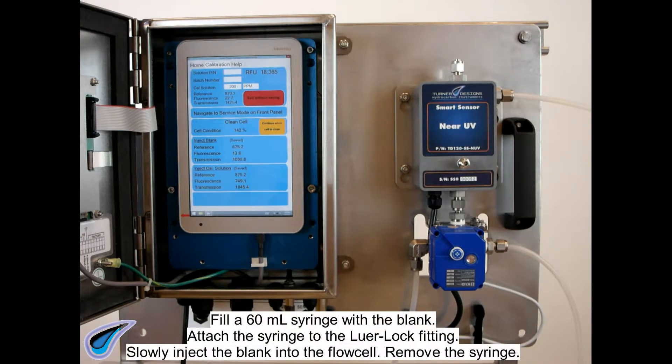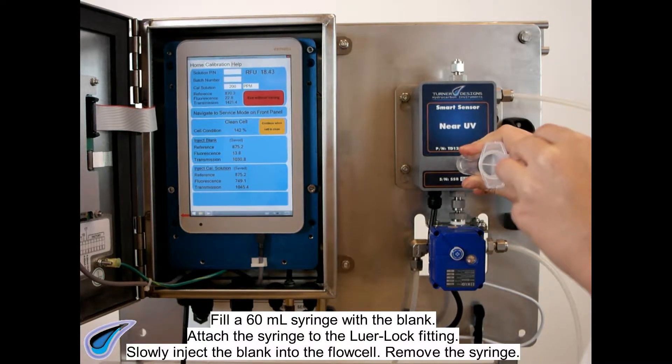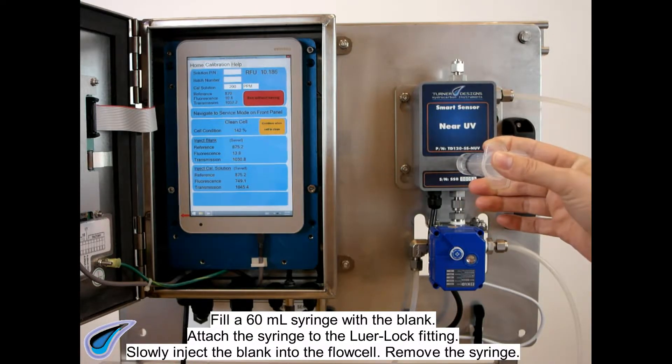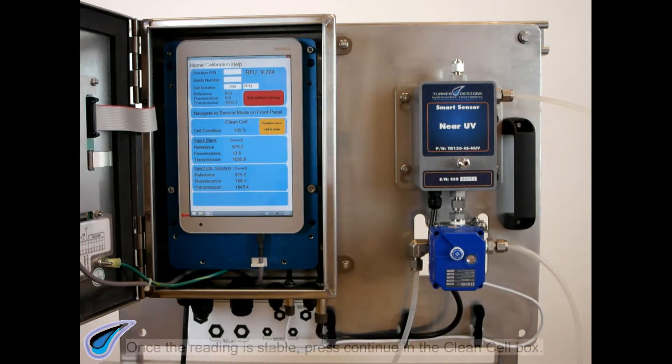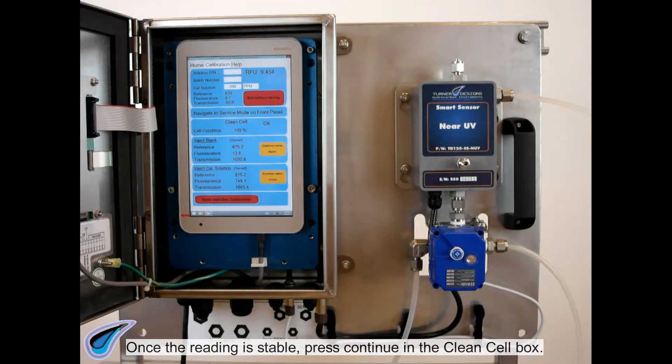Fill a 60 milliliter syringe with the blank. Attach the syringe to the Luer-Lock fitting and slowly inject the blank into the flow cell. Remove the syringe. Once the reading is stable, press the Continue button in the Clean Cell box.